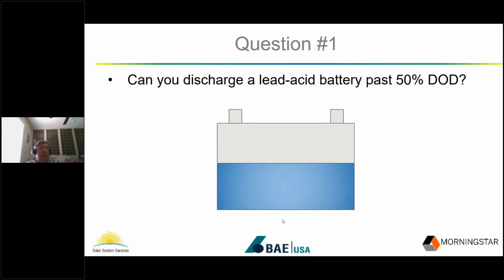You can absolutely use 80%, no problem. I've been in the solar industry for over 35 years, always use 80%. As a matter of fact, this is the LVD set point used by most controller manufacturers. Go to Morningstar, most of theirs are set to about 80%. I bring that up because I hear from people who don't know any better that you can't discharge a lead acid battery past 50%.